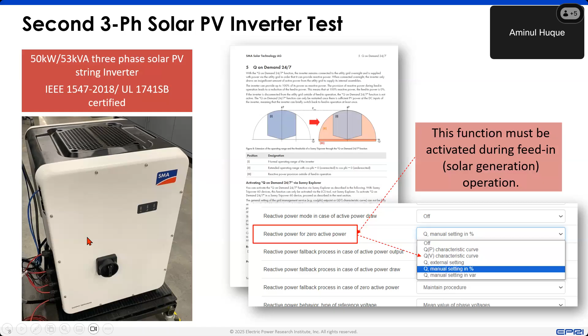So again, we configured that. Then we configured it with the volt-var curve shown on the left side, which is basically the 1547 category B default setting. And after that, we basically did the same thing. From low voltage, we went to high voltage, and then brought the voltage down, with slow changes, fast changes, different types of tests. Then we captured the reactive power output from the inverter and also the corresponding active power demand. One thing I'd like to highlight here: if you see the red dot, if we let the inverter go to its typical sleep mode, like sunset, and come back the next morning, it was taking roughly 4.9 watt.